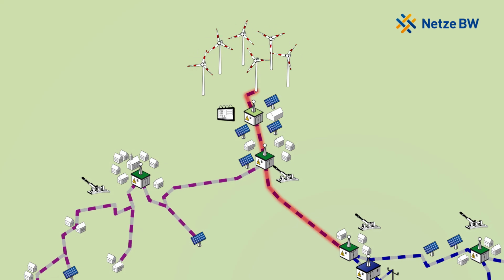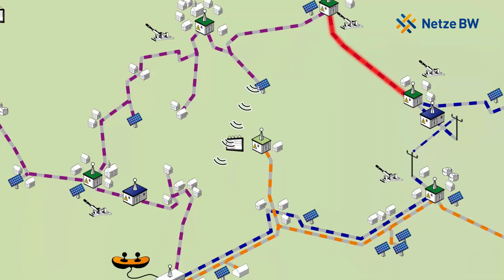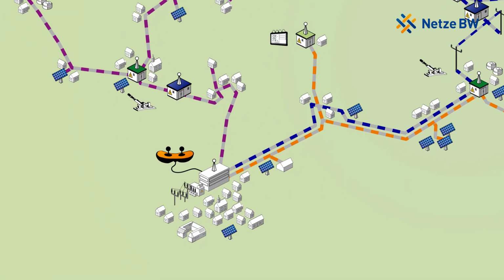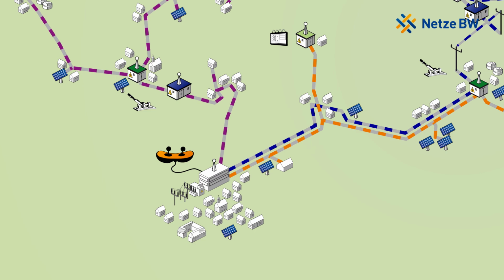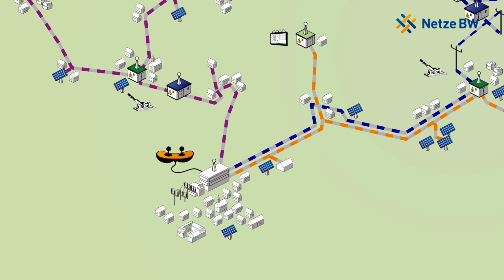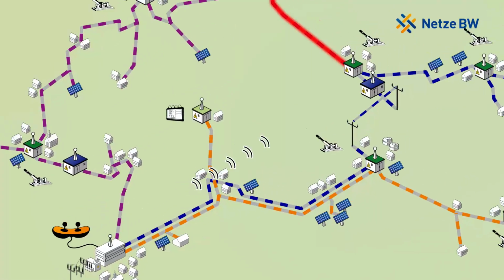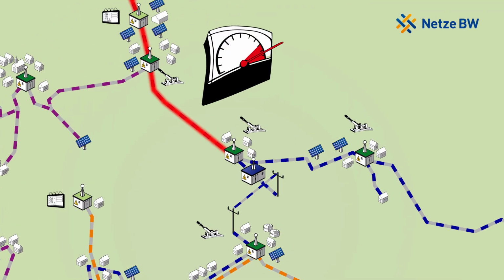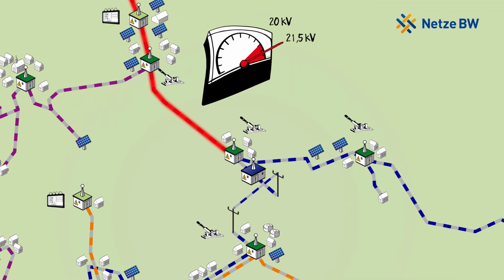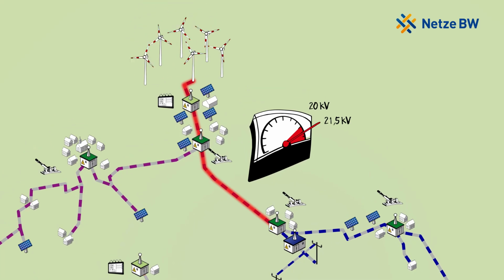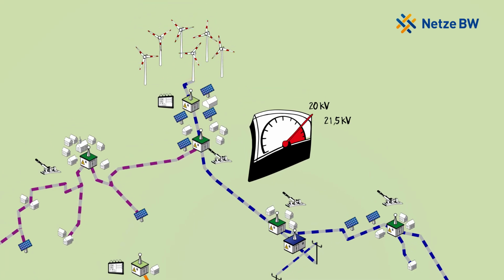Thanks to the distributed measuring instrumentation, the regional controller in the primary substation recognizes situations in which high power feed-in occurs. If the voltage level rises too high, the controller transmits a command to the line voltage regulator to lower the voltage level. The controller steps the voltage down and the grid bottleneck is eliminated.